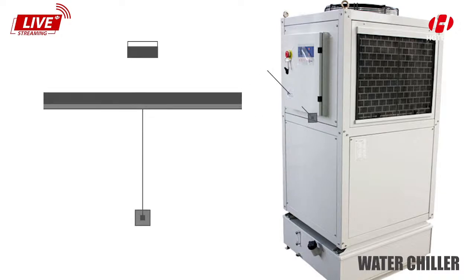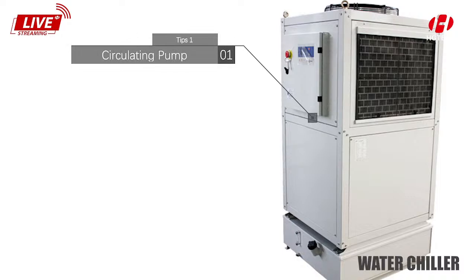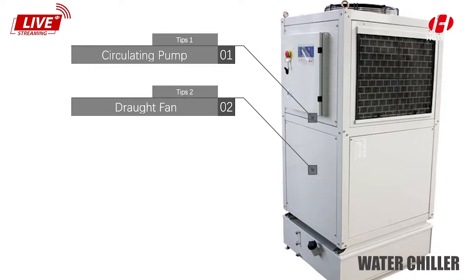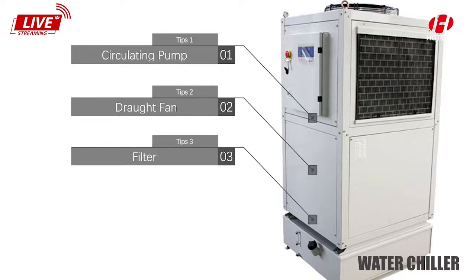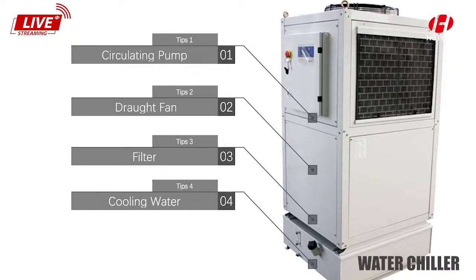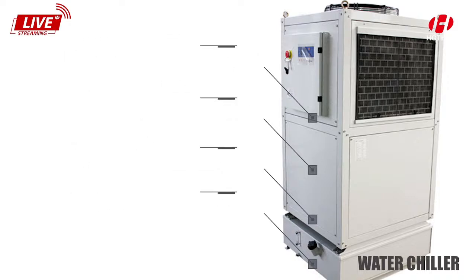Monthly inspections. Check the circulating pump and interface connections for abnormal noise and water seepage. Check the draft fan and compressor operation for abnormal noise. Check the filter inside the cooler. If there are foreign objects, please clean them in time. Replace the cooling water according to the water quality. After 3 months, to replace the cooling water, you should use distilled water or deionized water.